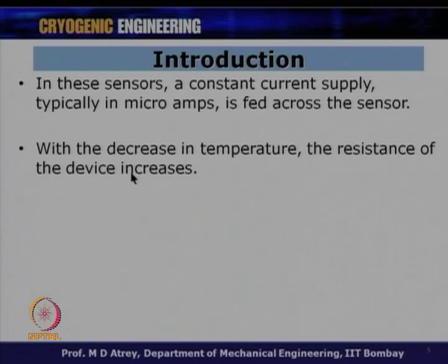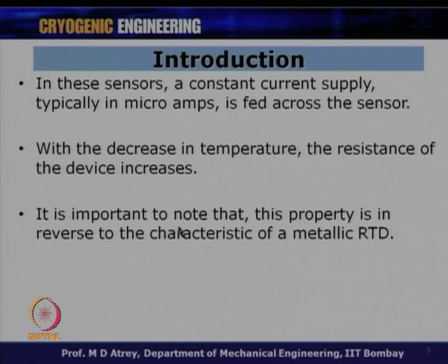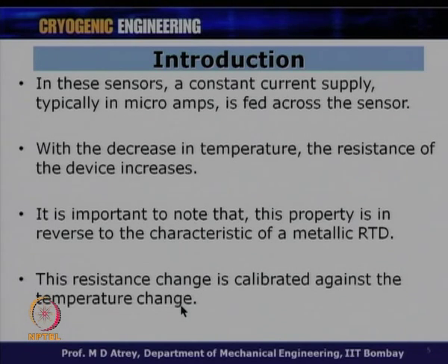With a decrease in temperature, the resistance of the device increases. This is important to note: it is the reverse of metallic RTD behavior. In metallic RTDs, resistance decreased as temperature decreased. In non-metallic sensors, resistance increases as temperature decreases. This resistance change is calibrated against temperature change, so resistance becomes a function of temperature and one can fit a calibration curve.